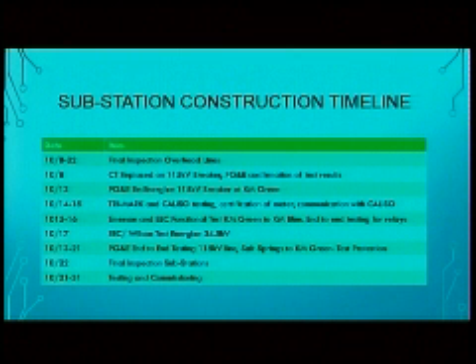Another important part of putting that on is in discussions with PG&E. PG&E needs load from us to finish their final end-to-end testing. They now have determined that pretty much our reactive power is enough of a load for them to test their relays. So this end-to-end testing that Michael's describing, we intend to, when we energize the 35 kV, have PG&E at Green, and they will then do their testing. That should be enough for them to finish their end-to-end testing, and by test energizing the 35 kV, we give them what they need.